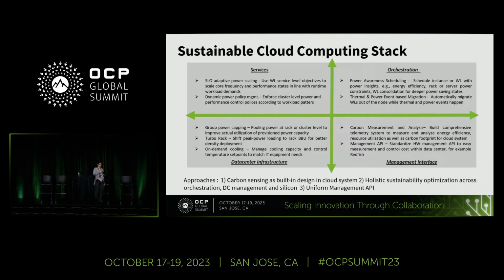And then I think Brijesh stressed on this power capping, which is group level power capping. We have built a very sophisticated way of doing that. If you look at some of our data center customers, their power utilization in the racks is between 30 to 40, or maybe maximum 50%. They are over-provisioning their racks for power. Now, what we are telling them is you could go to the maximum, to the power budget, but you have to have some mechanism in place for when it exceeds the budget.